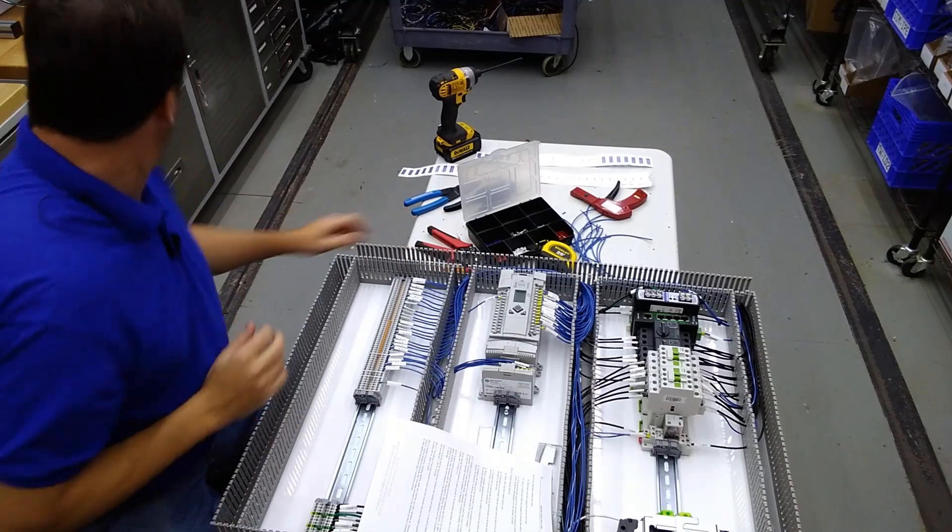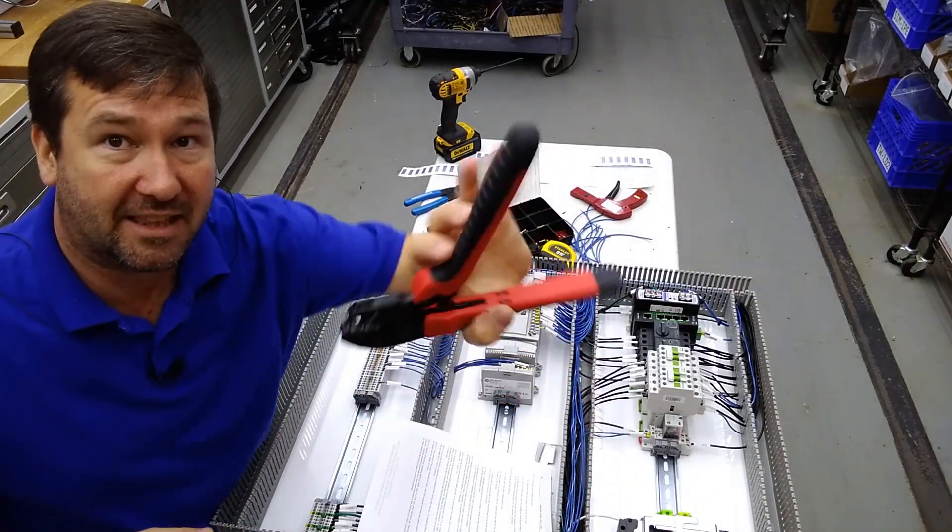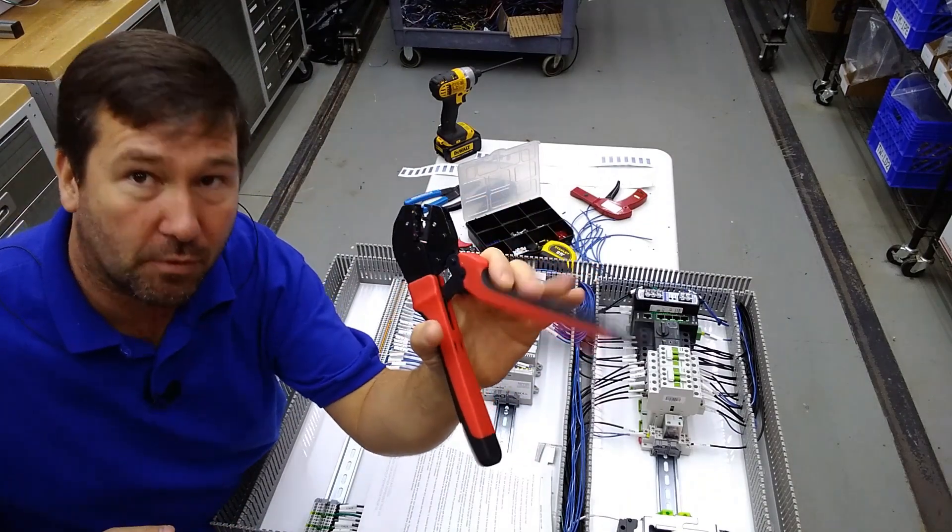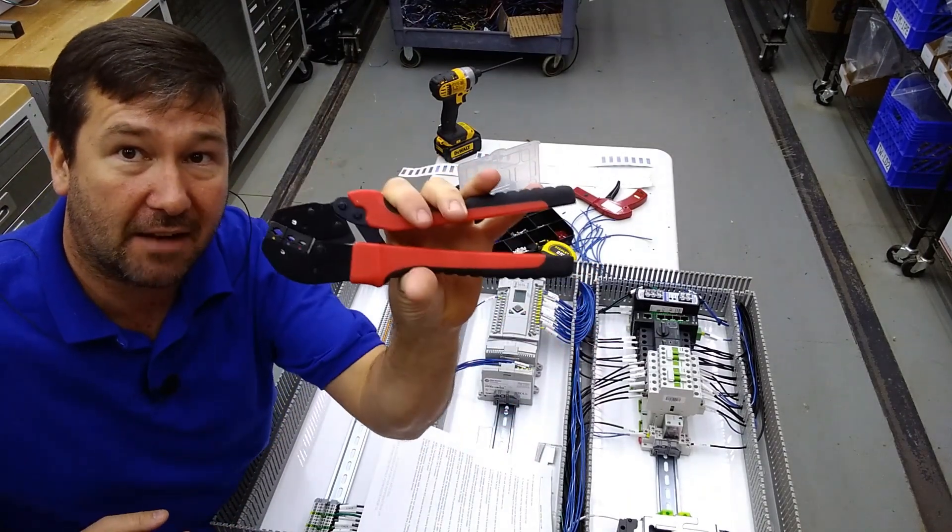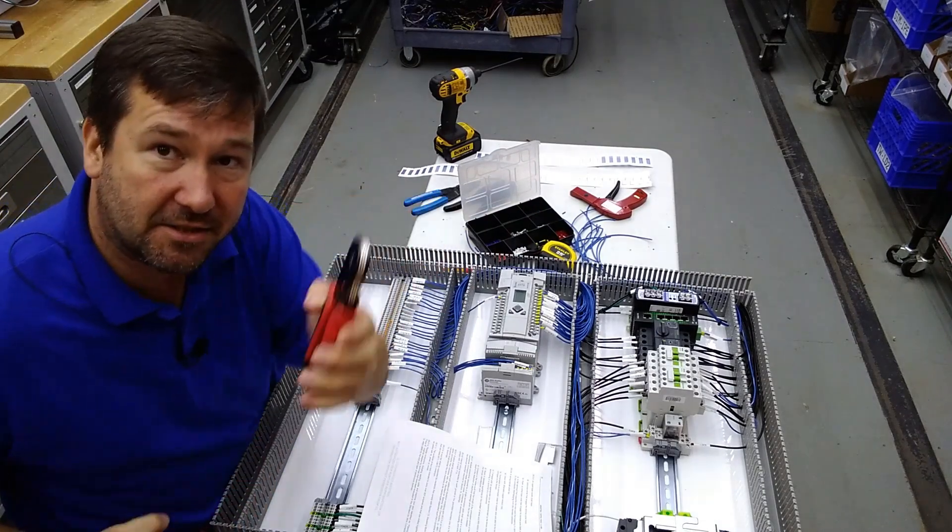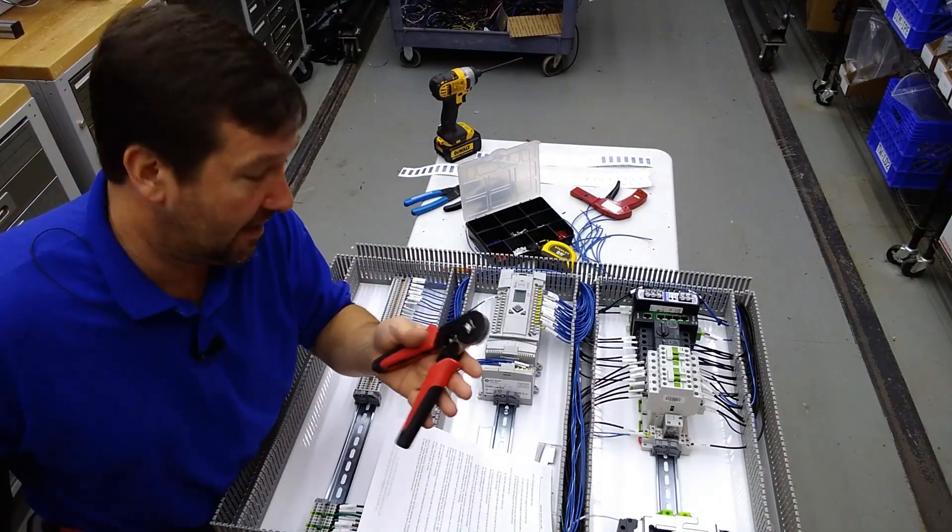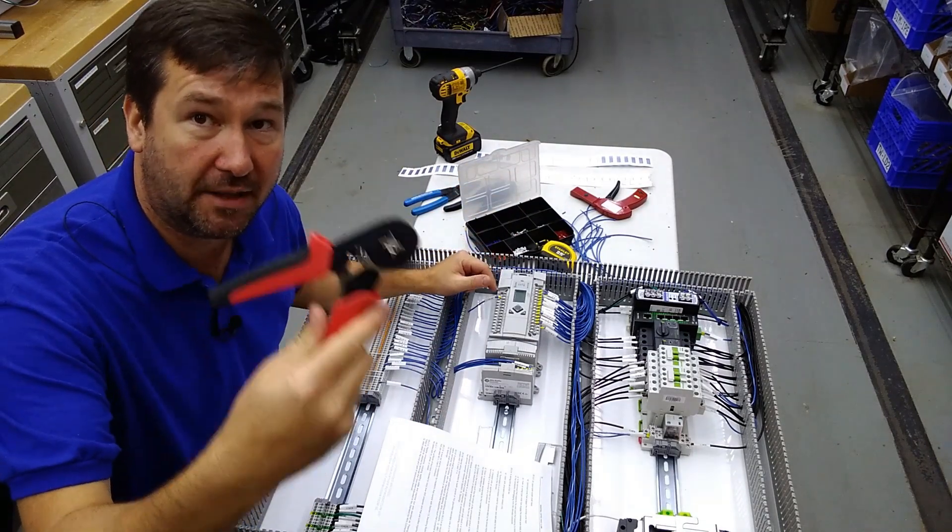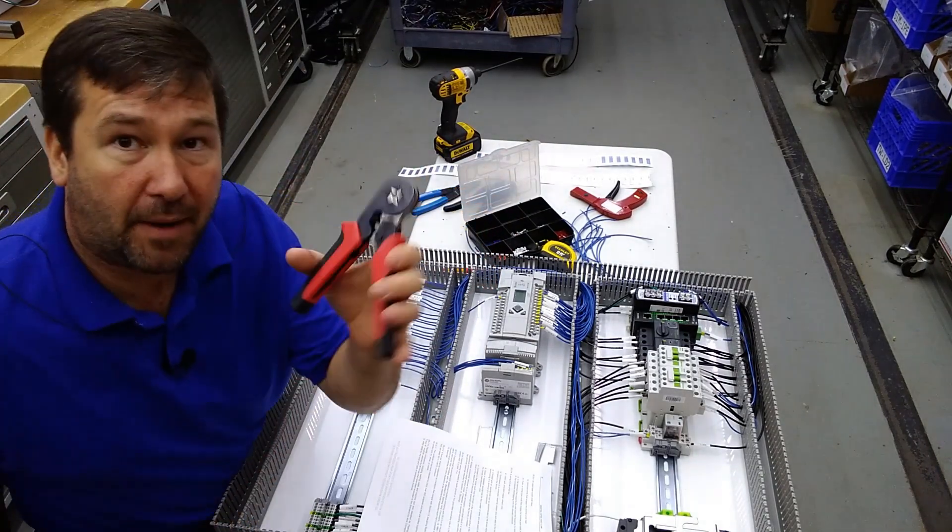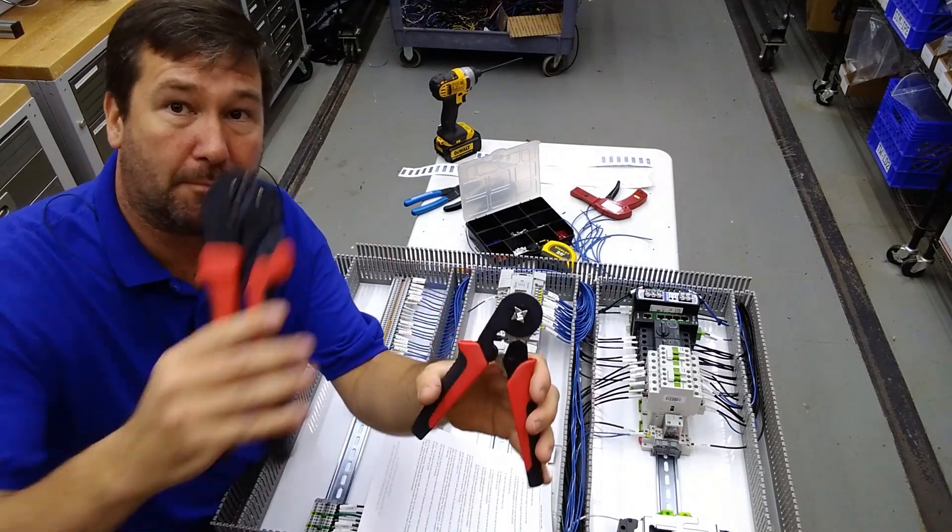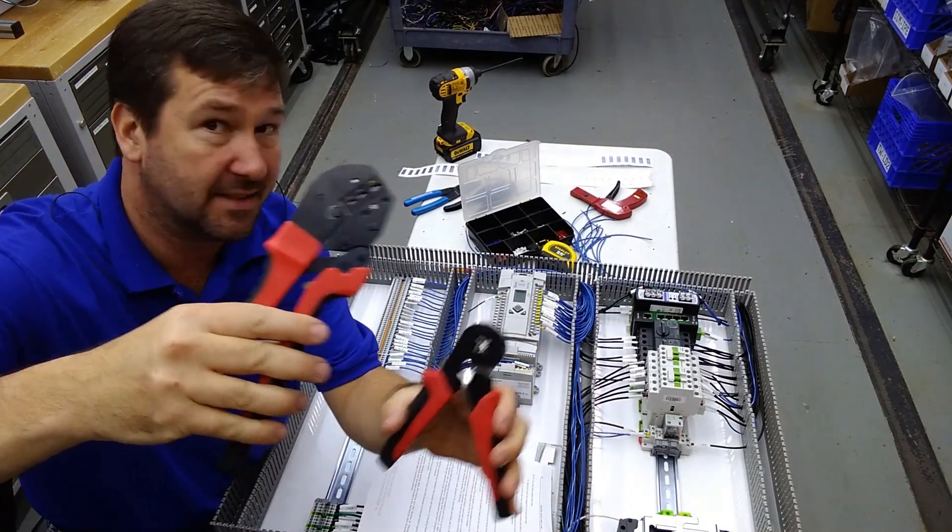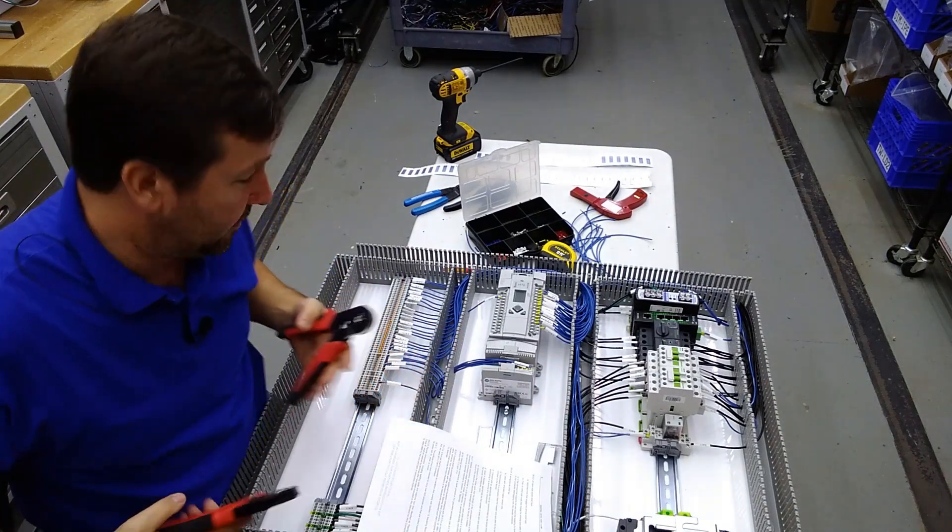So for example, I used to have a ferrule crimp tool like this, and this thing all day really kills your hands. So if you have one of these, throw it out and get you something like this. But the other big thing about what they're saying there is this needs to be recommended by the ferrule manufacturer. If I buy this ferrule crimping tool but I'm buying ferrules that this manufacturer recommends that will not meet the UL requirements.